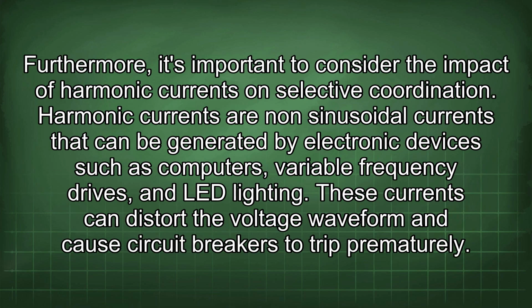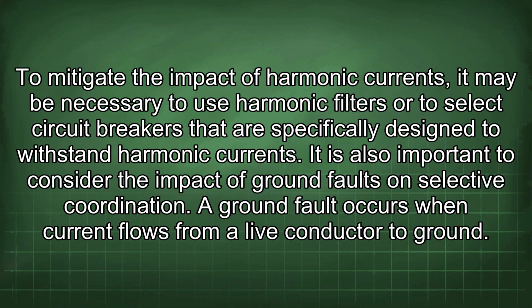Furthermore, it's important to consider the impact of harmonic currents on selective coordination. Harmonic currents are non-sinusoidal currents that can be generated by electronic devices such as computers, variable frequency drives, and LED lighting. These currents can distort the voltage waveform and cause circuit breakers to trip prematurely. To mitigate the impact of harmonic currents, it may be necessary to use harmonic filters or to select circuit breakers that are specifically designed to withstand harmonic currents.